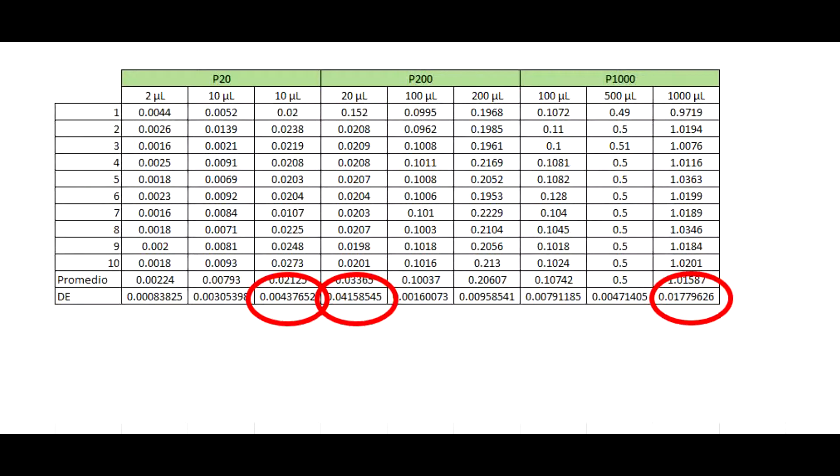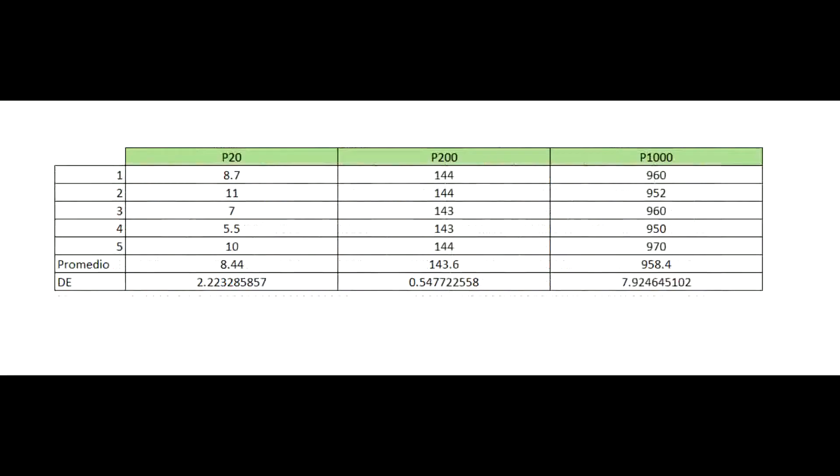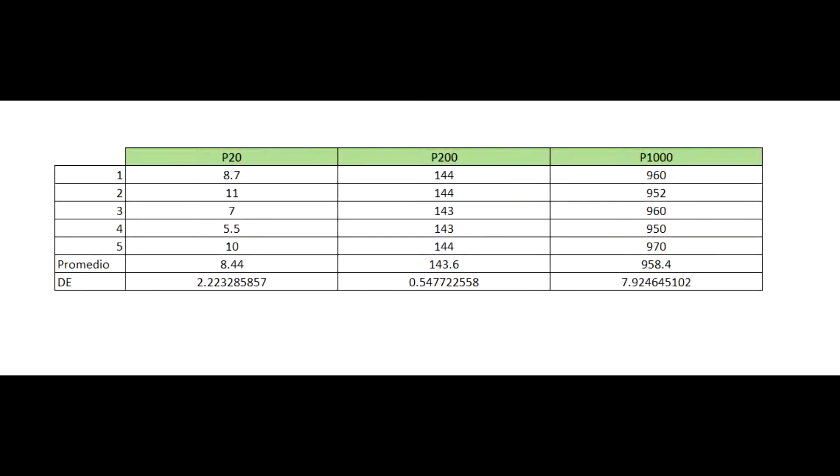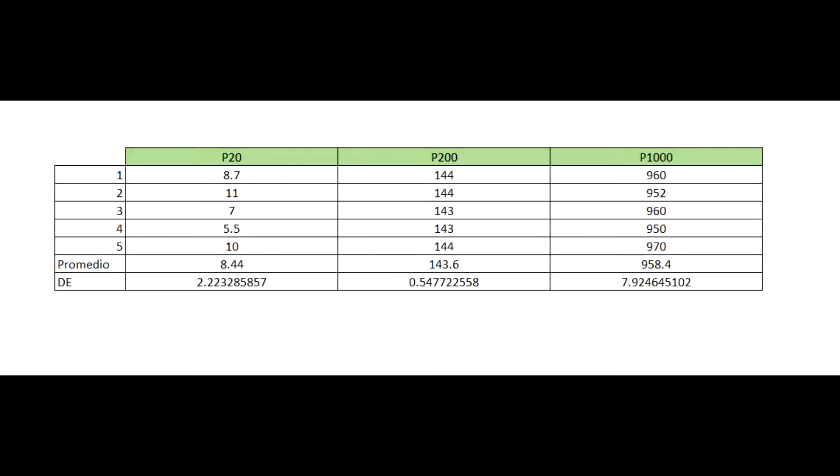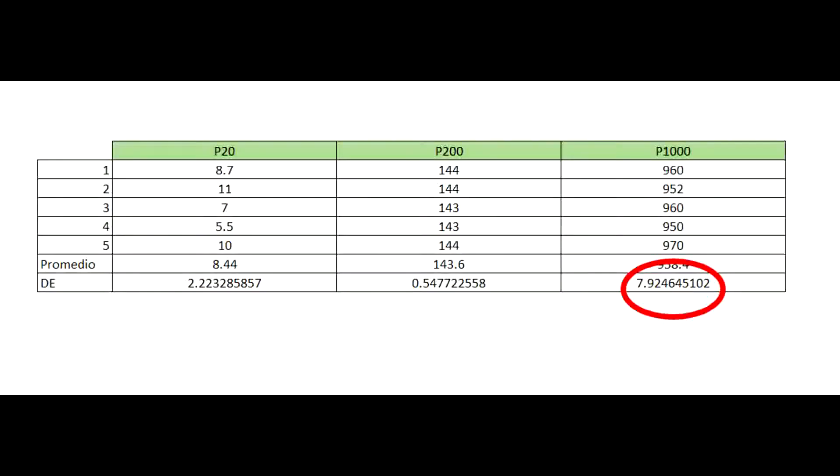In this case, we can see that the largest standard deviation value of each micropipet is located in the limits of each kind of micropipet. In the second experiment, the standard deviation values are different, but we can see that the largest value of standard deviation is from the micropipet of 1000 microliters.